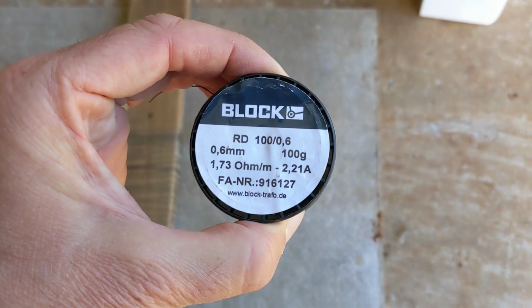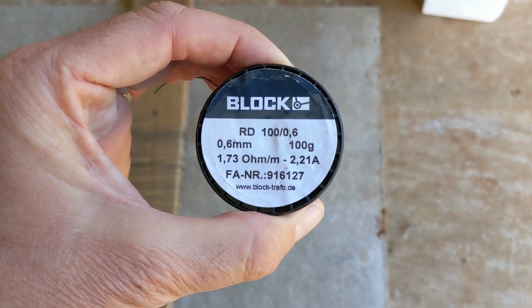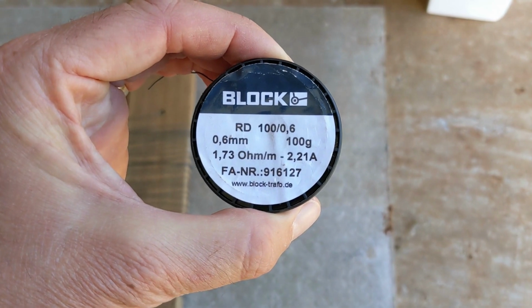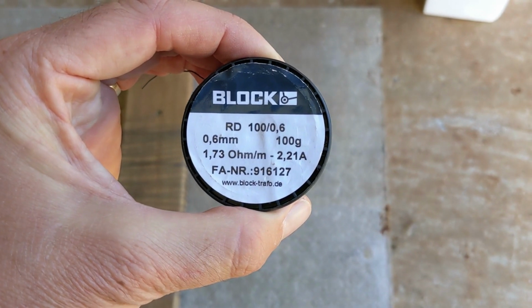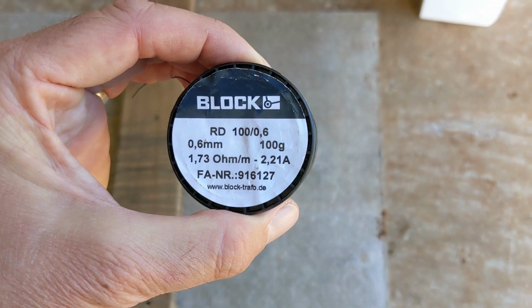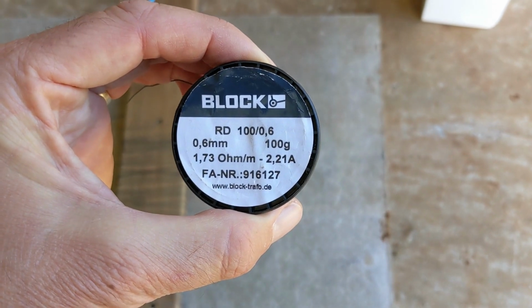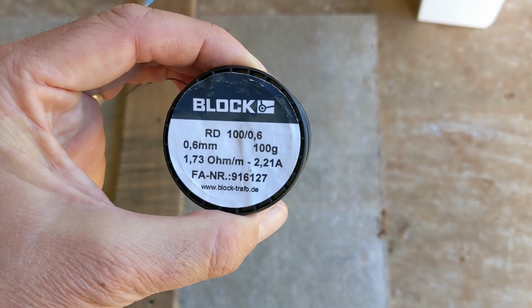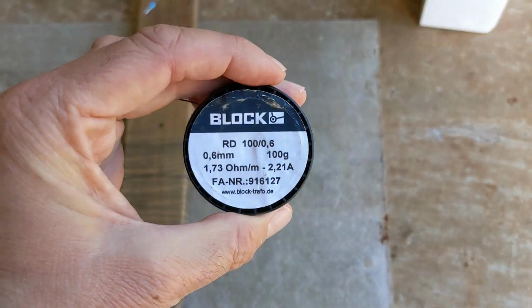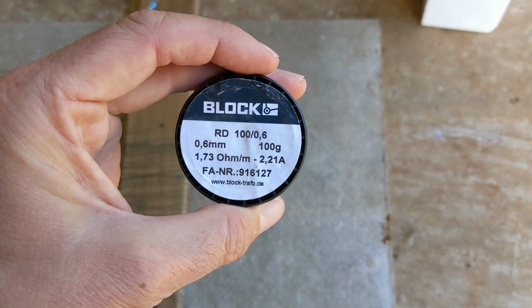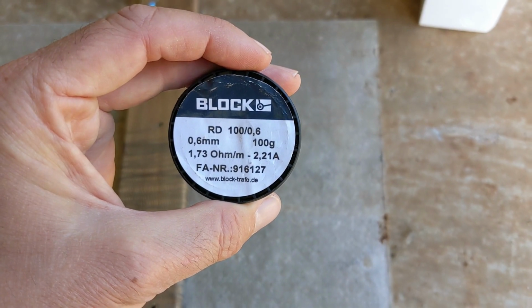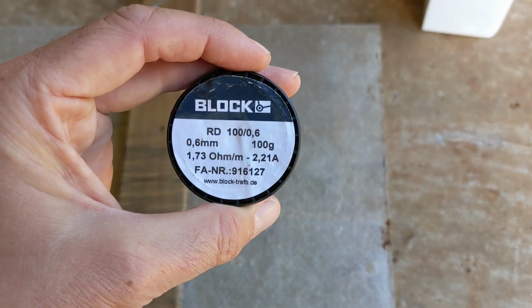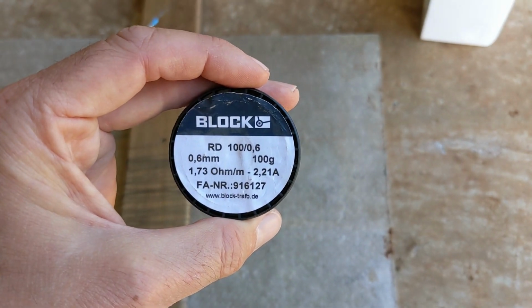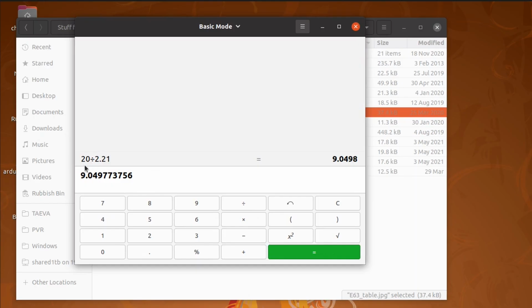It's designed with a resistance, a bit like nichrome wire, but it's a slightly different stuff. And so you can see here that we have 1.73 ohms per meter and that it can take 2.21 amps. So what I want to do is to discharge at 2.21 amps through this wire. To do that, I need to get a certain length of it, and I need to figure that out by figuring out how many ohms I need at 20 volts to run 2.2 amps. So here we go, 20 volts divided by 2.21 is 9.04 ohms.